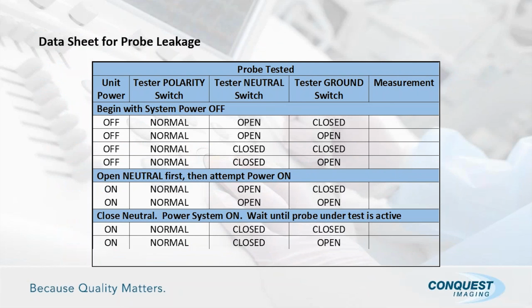Here's the probes tested. You have to do this on each individual probe. So again, I recommend testing the probes while you're in the off, normal, open, closed position. Do all the probes while you're in that condition so you don't have to turn the system on and off, on and off, on and off. It'll save you a significant amount of time.